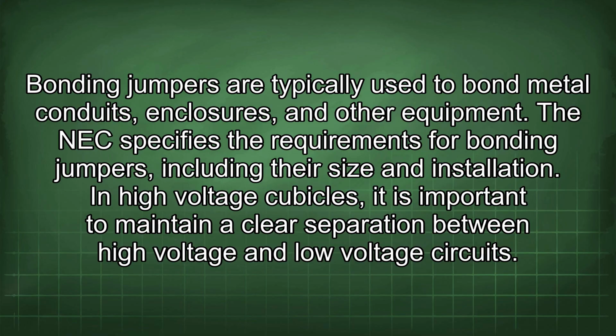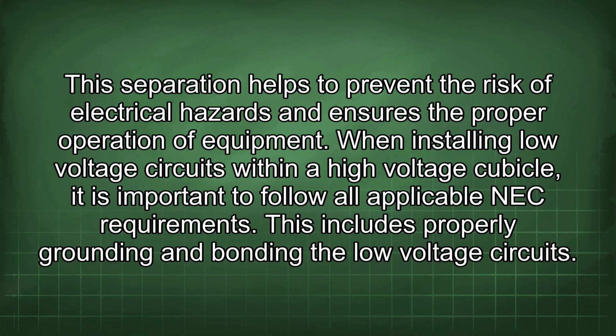In high voltage cubicles, it is important to maintain a clear separation between high voltage and low voltage circuits. This separation helps to prevent the risk of electrical hazards and ensures the proper operation of equipment. When installing low voltage circuits within a high voltage cubicle, it is important to follow all applicable NEC requirements. This includes properly grounding and bonding the low voltage circuits.